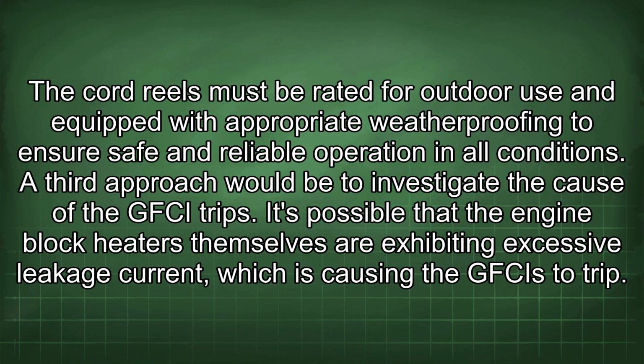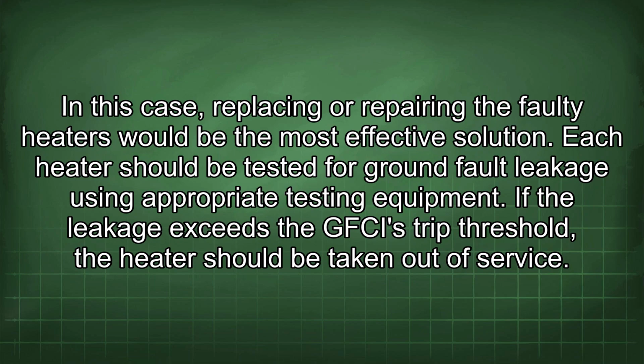in all conditions. A third approach would be to investigate the cause of the GFCI trips. It is possible that the engine block heaters themselves are exhibiting excessive leakage current, which is causing the GFCIs to trip. In this case, replacing or repairing the faulty heaters would be the most effective solution. Each heater should be tested for ground fault leakage using appropriate testing equipment. If the leakage exceeds the GFCI's trip threshold, the heater should be taken out of service.